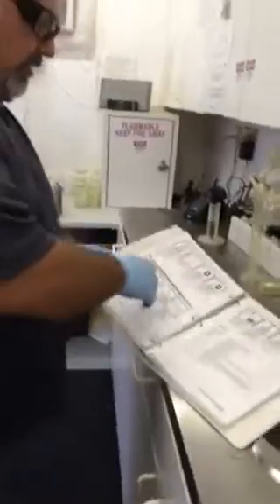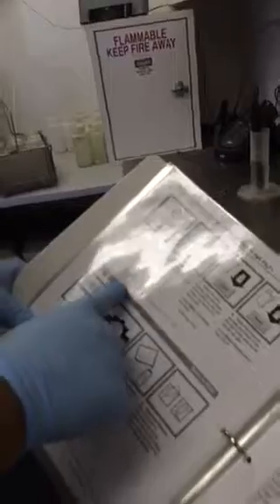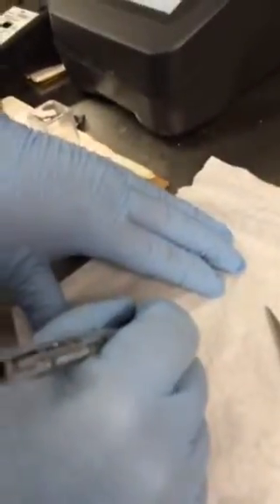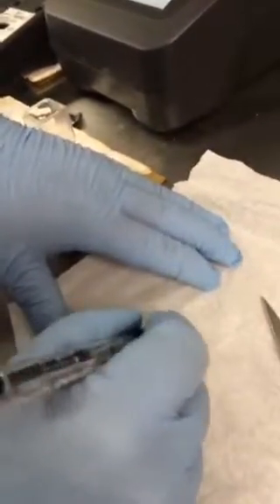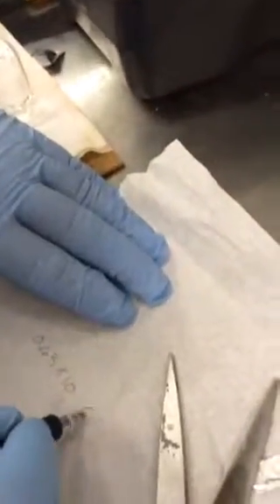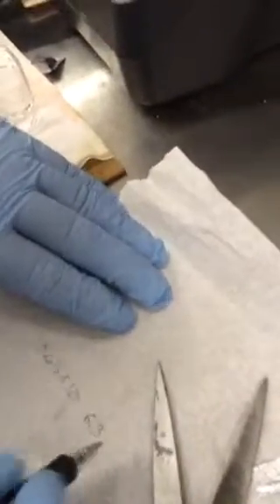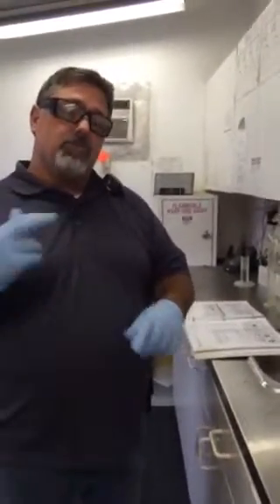So, based on our test here, because we did a 10% dilution sample, we're going to multiply the result by 10 to get our result. So 0.63 times 10 is going to be 6.3, okay? So 6.3 is what you're going to record for your phosphate. All right?